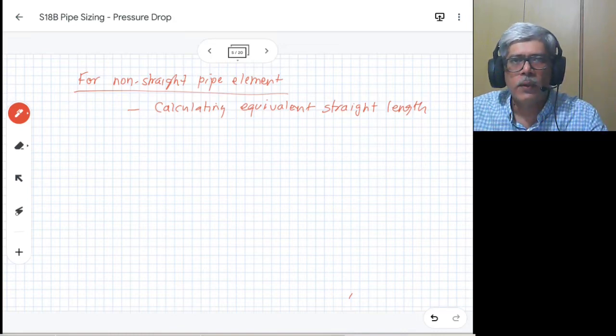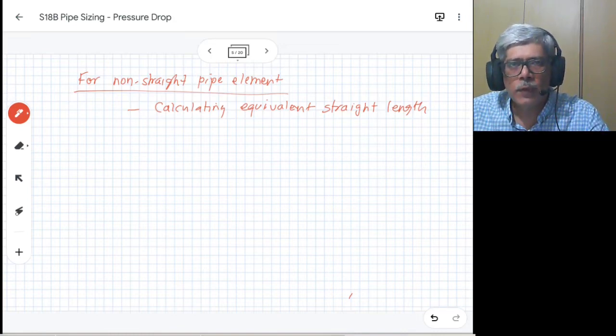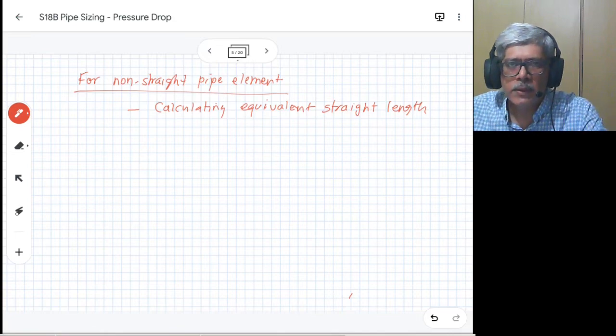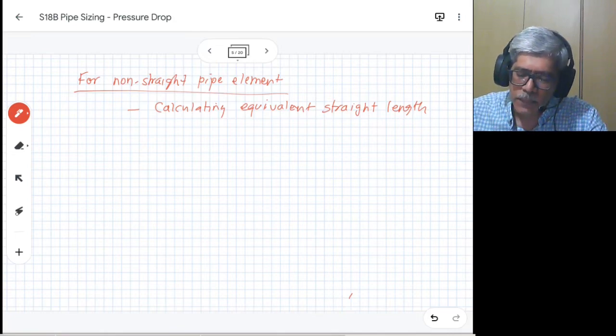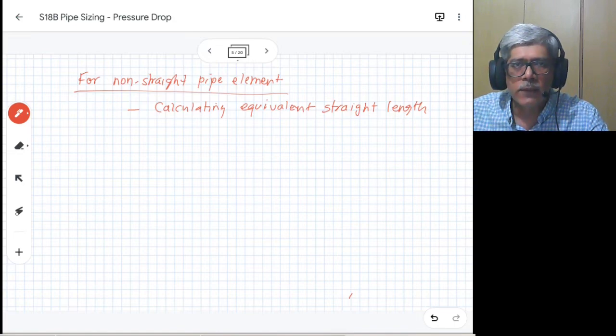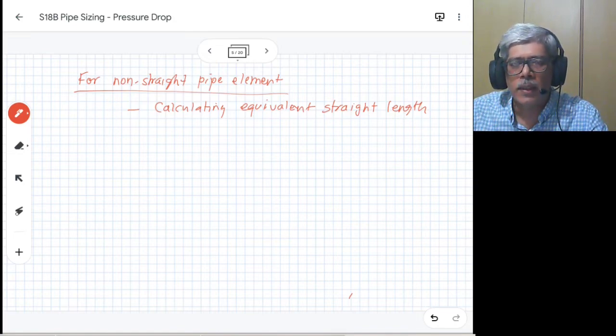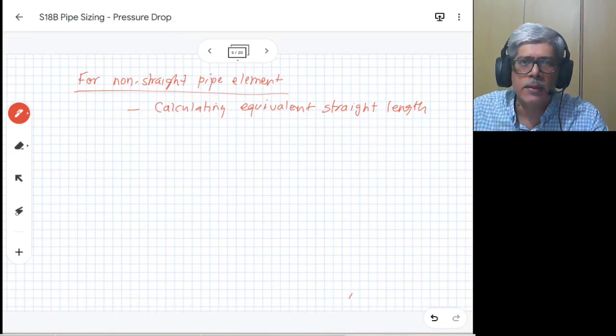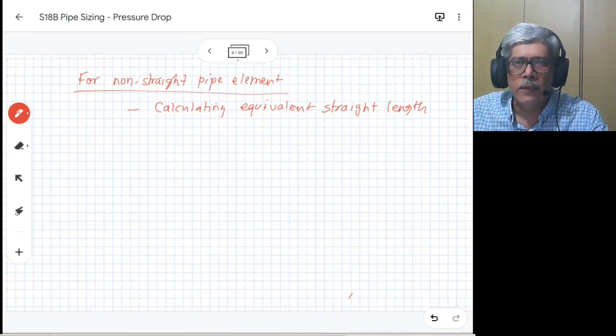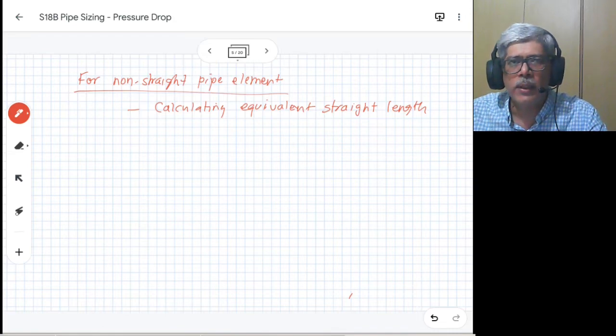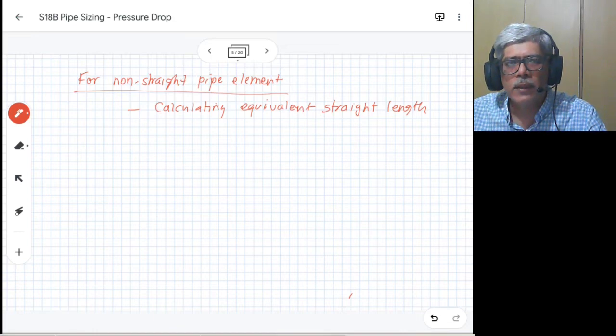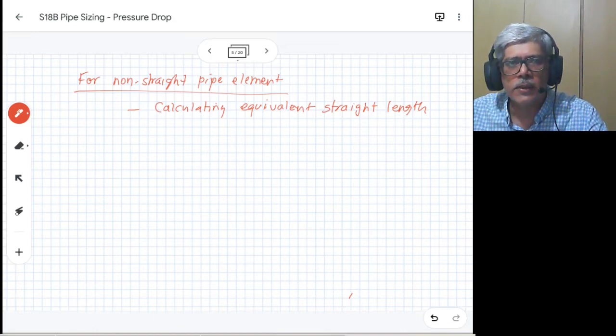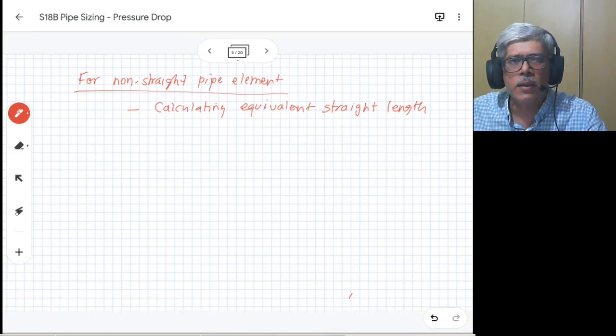At the end of this process, for a given pipe size, you will get the equivalent straight pipeline length. For that pipeline, using Darcy's equation, we can find out the pressure drop. We consider how many different sizes of pipelines are in your system, so for each pipeline size you will do the pressure drop calculation separately, add all those pressure drops, and you will get the total pressure drop for the system.